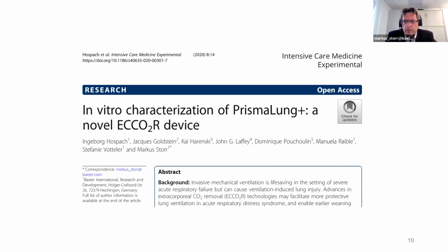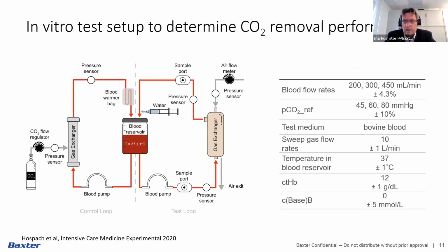We have characterized our novel PRISMALUNG Plus device extensively with respect to CO2 removal capacity in an in vitro setting. So we investigated the impact of operating conditions such as blood flow, sweep gas flow, or CO2 partial pressure in the blood. You see here the experimental setup we've used. It was a closed loop circuit in which a continuous infusion of CO2 balanced the CO2 removal from the test gas exchanger in steady state conditions.